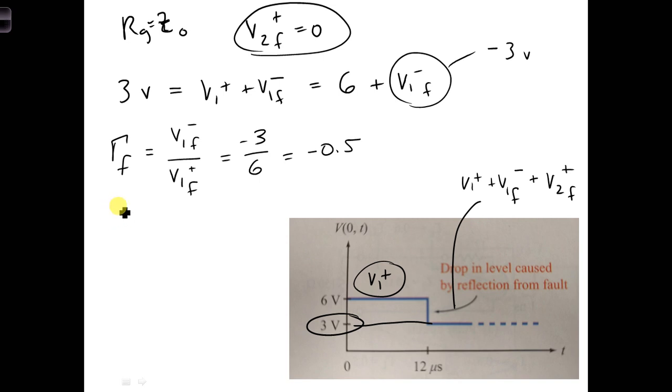Now, we can also write this as minus 0.5 is also equal to RLF minus Z naught over RLF plus Z naught, where RLF is the total load impedance at the location of the fault. Meaning, it's not RF, because RF is just the value of the resistor going between the two conductors. This is the total load impedance at the fault.